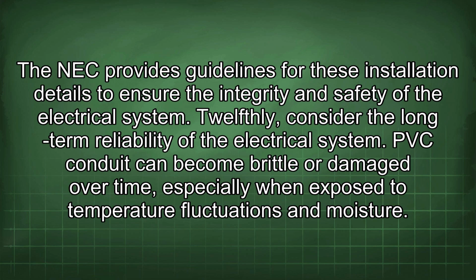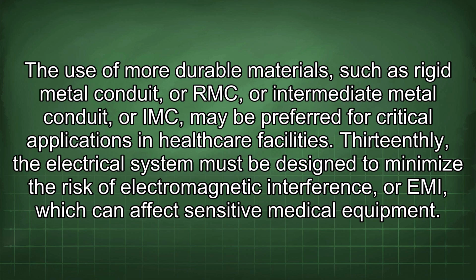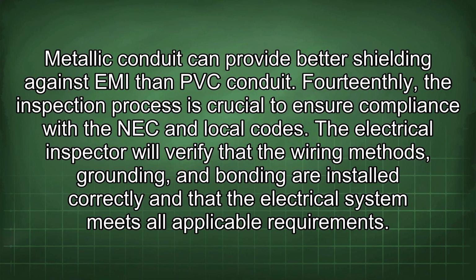Twelfthly, consider the long-term reliability of the electrical system. PVC conduit can become brittle or damaged over time, especially when exposed to temperature fluctuations and moisture. The use of more durable materials, such as rigid metal conduit, or RMC, or intermediate metal conduit, or IMC, may be preferred for critical applications in healthcare facilities. Thirteenthly, the electrical system must be designed to minimize the risk of electromagnetic interference, or EMI, which can affect sensitive medical equipment. Metallic conduit can provide better shielding against EMI than PVC conduit.